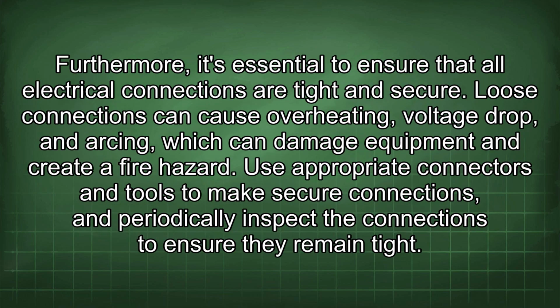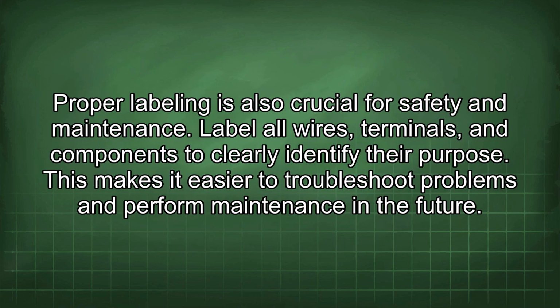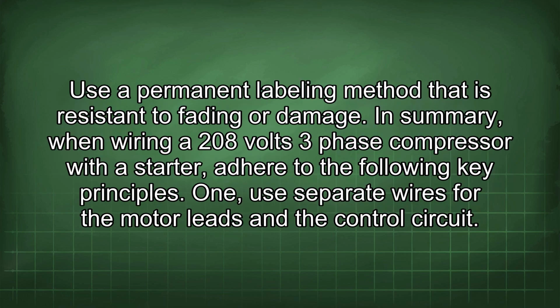Furthermore, it's essential to ensure that all electrical connections are tight and secure. Loose connections can cause overheating, voltage drop, and arcing, which can damage equipment and create a fire hazard. Use appropriate connectors and tools to make secure connections and periodically inspect the connections to ensure they remain tight. Proper labeling is also crucial for safety and maintenance. Label all wires, terminals, and components to clearly identify their purpose. This makes it easier to troubleshoot problems and perform maintenance in the future. Use a permanent labeling method that is resistant to fading or damage.